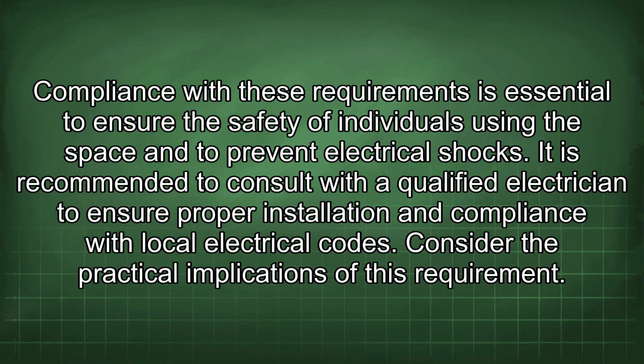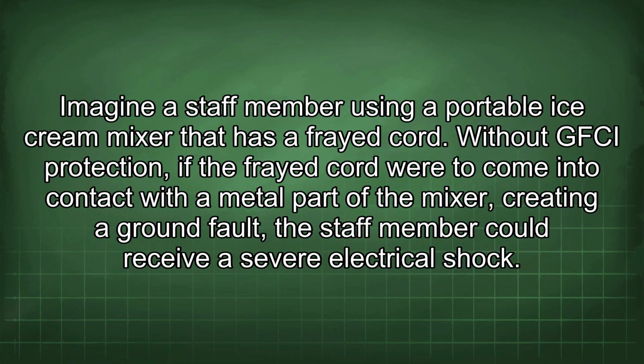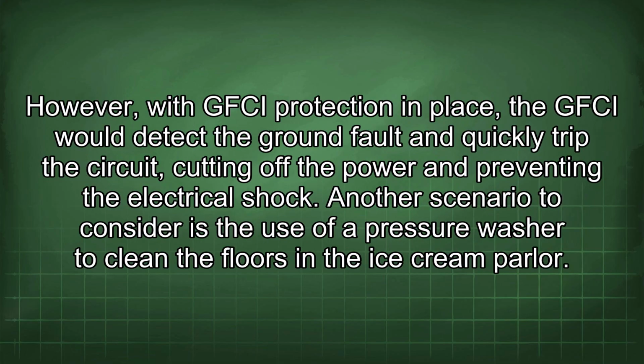Consider the practical implications of this requirement. Imagine a staff member using a portable ice cream mixer that has a frayed cord. Without GFCI protection, if the frayed cord were to come into contact with a metal part of the mixer, creating a ground fault, the staff member could receive a severe electrical shock. However, with GFCI protection in place, the GFCI would detect the ground fault and quickly trip the circuit, cutting off the power and preventing the electrical shock.